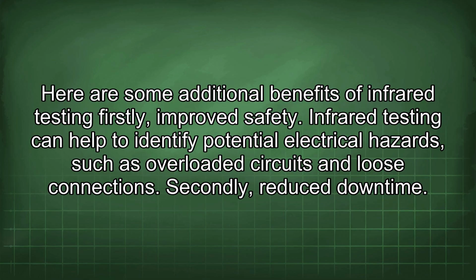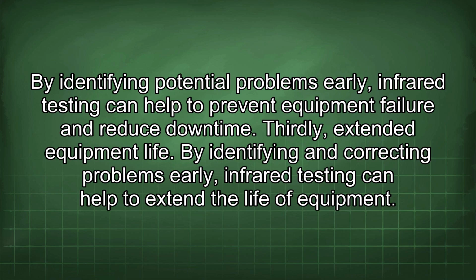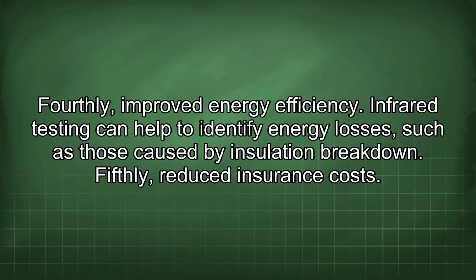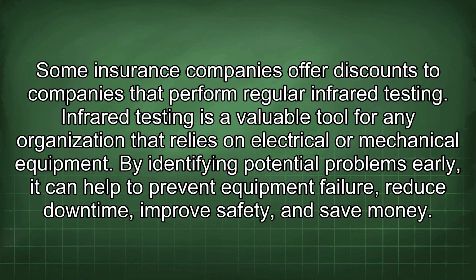Firstly, improved safety. Infrared testing can help to identify potential electrical hazards such as overloaded circuits and loose connections. Secondly, reduced downtime. By identifying potential problems early, infrared testing can help to prevent equipment failure and reduce downtime. Thirdly, extended equipment life. By identifying and correcting problems early, infrared testing can help to extend the life of equipment. Fourthly, improved energy efficiency. Infrared testing can help to identify energy losses, such as those caused by insulation breakdown. Fifthly, reduced insurance costs. Some insurance companies offer discounts to companies that perform regular infrared testing.